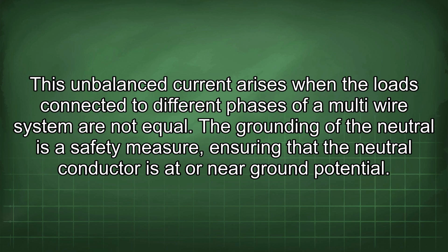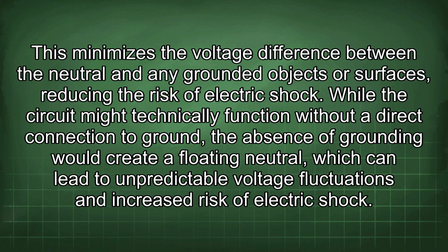The grounding of the neutral is a safety measure, ensuring that the neutral conductor is at or near ground potential. This minimizes the voltage difference between the neutral and any grounded objects or surfaces, reducing the risk of electric shock. While the circuit might technically function without a direct connection to ground, the absence of grounding would create a floating neutral, which can lead to unpredictable voltage fluctuations and increased risk of electric shock.